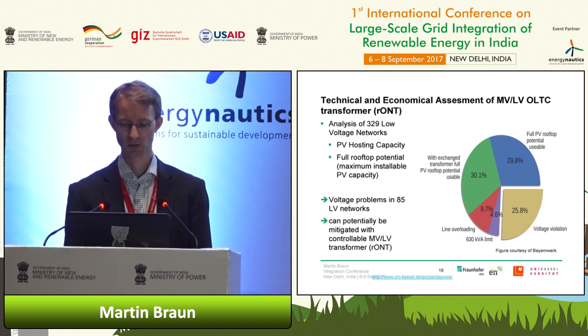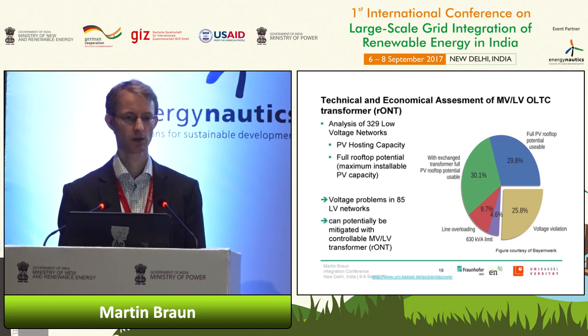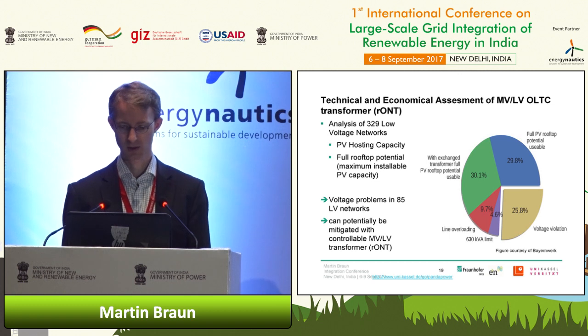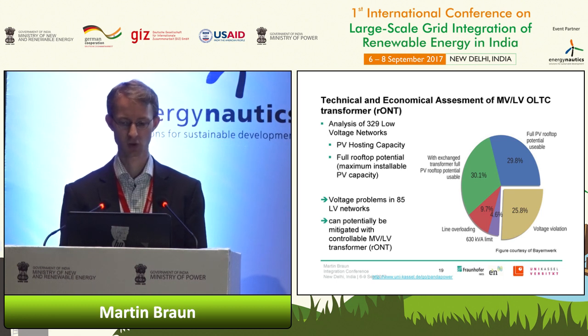In a quarter of the grids, the full PV rooftop potential can be used as is. In 30% of them, it's easy to just exchange the distribution transformer, so that's not a big deal. Then we have some overloading issues, and for the voltage-related issues we look at on-load tap changing transformers.